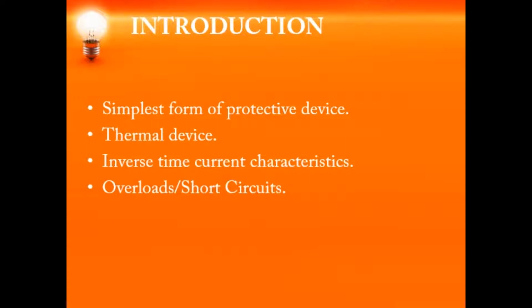It is the cheapest as well as the oldest protective device, which interrupts the current under overload or short circuit conditions. So it is a thermal device which possesses an inverse time current characteristic. That means the operating time will decrease as the fault current increases. And this fuse is designed in such a way that it can carry the working current safely, and whenever there is a fault it has to break.